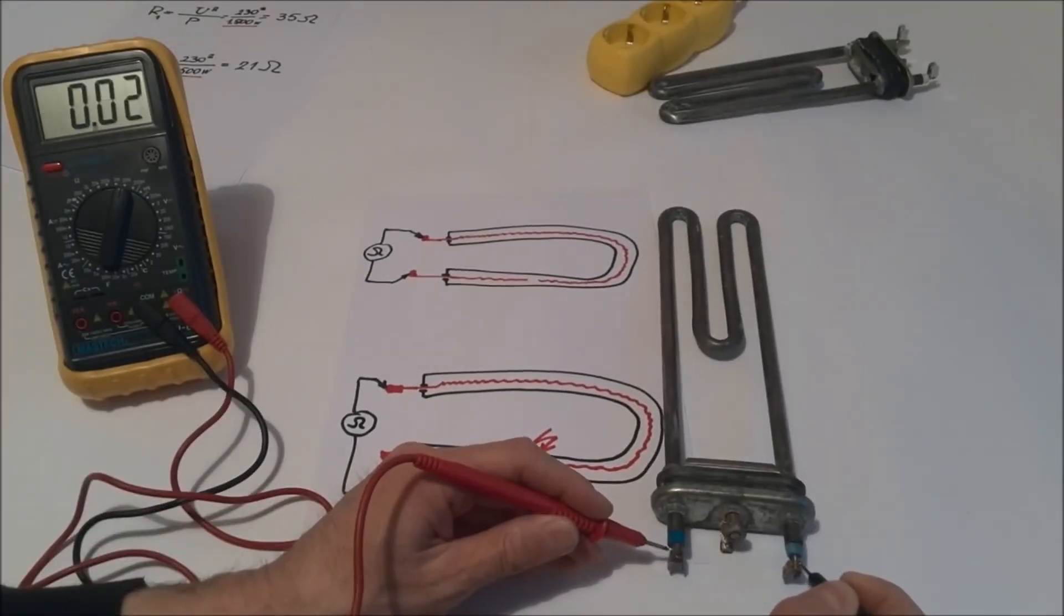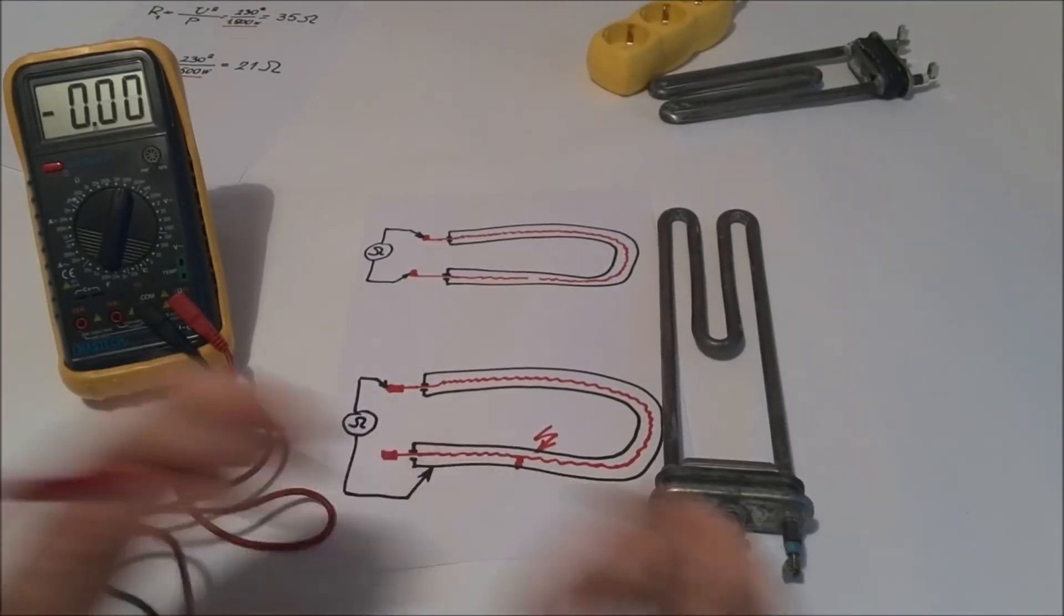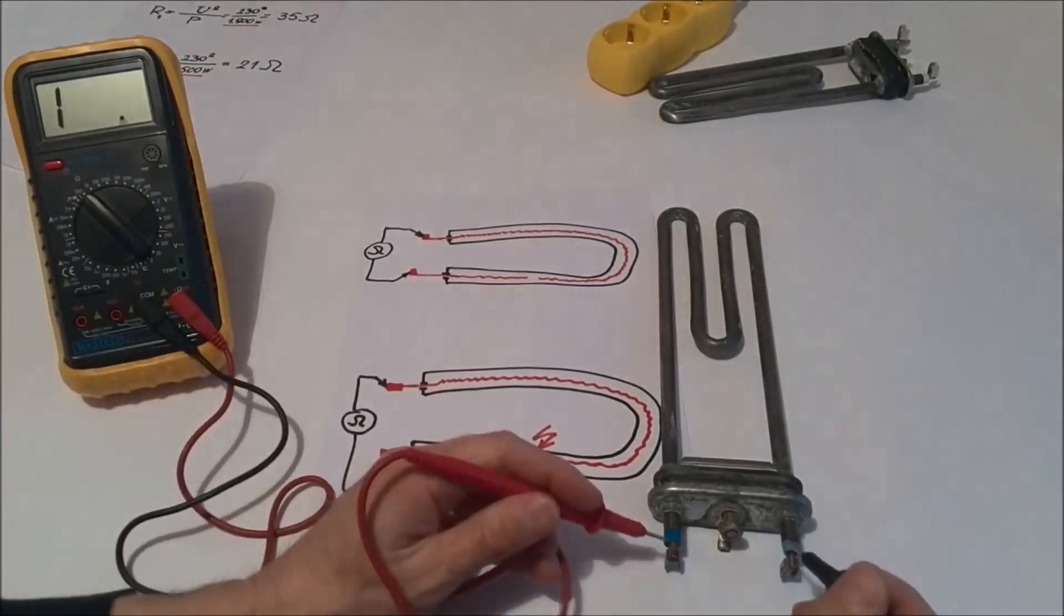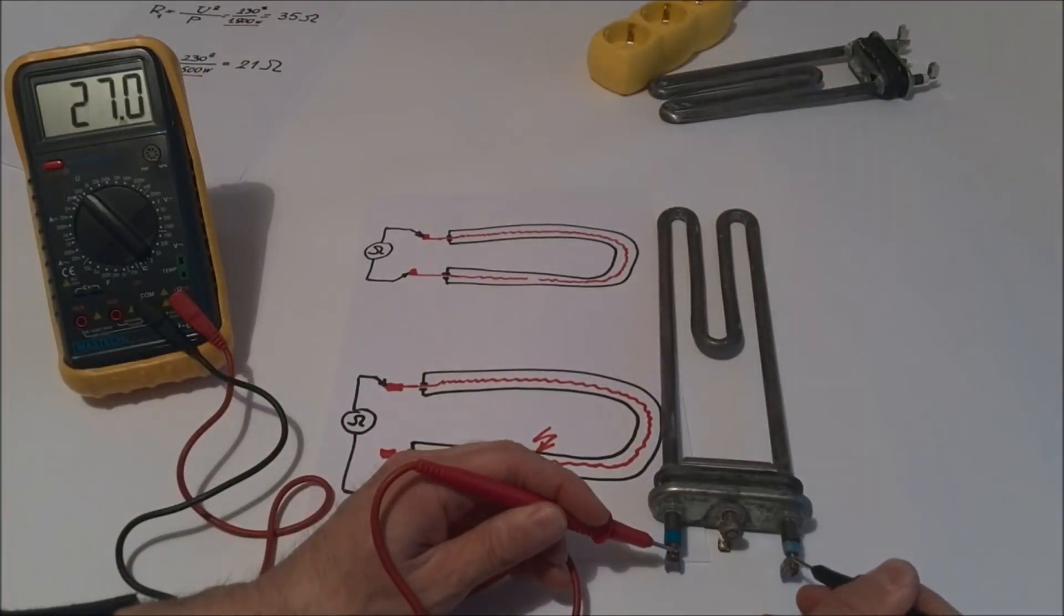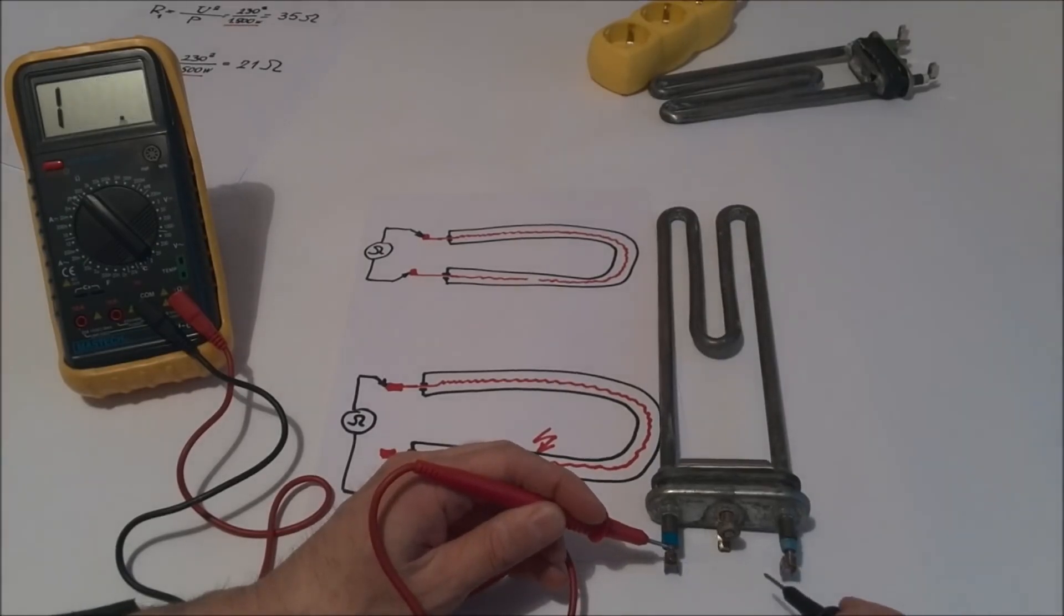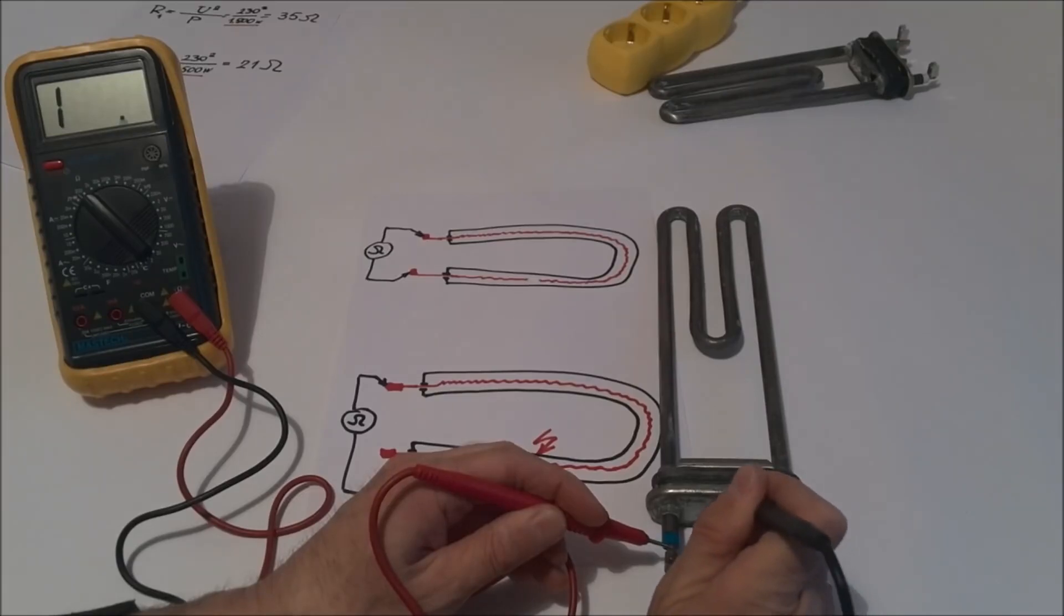Now we measure resistance. We will now reduce the scope. The first measurement indicates that the heater is functional, so it is not interrupted, but we must also check that the heating thread is not somewhere in contact with the cover.